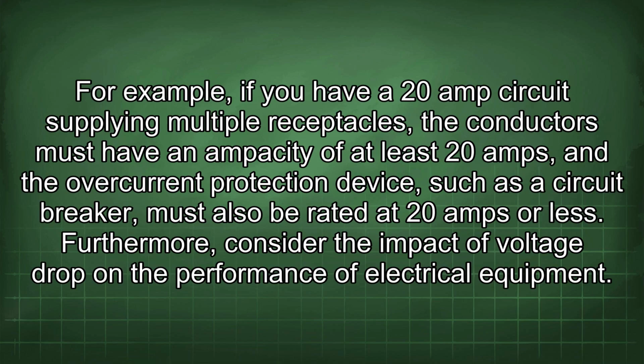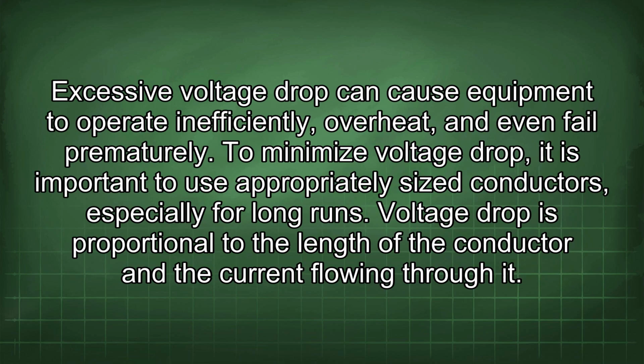For example, if you have a 20 amp circuit supplying multiple receptacles, the conductors must have an ampacity of at least 20 amps, and the overcurrent protection device, such as a circuit breaker, must also be rated at 20 amps or less. Furthermore, consider the impact of voltage drop on the performance of electrical equipment. Excessive voltage drop can cause equipment to operate inefficiently, overheat, and even fail prematurely.